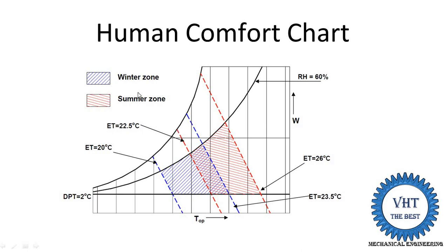Now focusing on the summer zone: the red colored line on the chart indicates the comfortable zone for human beings. This red line indicates an effective temperature of 22.5 degrees centigrade, and another red line indicates 26 degrees centigrade. The relative humidity range shown is from 30 to 60 percent. This red zone indicates the comfortable range for summer seasons.